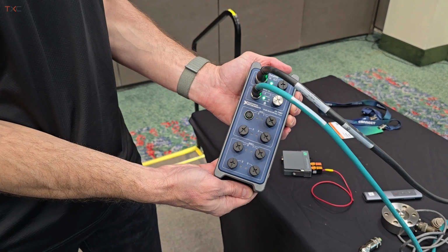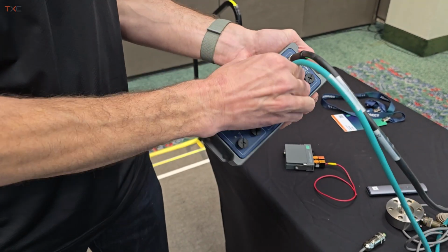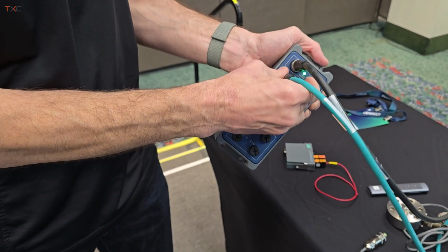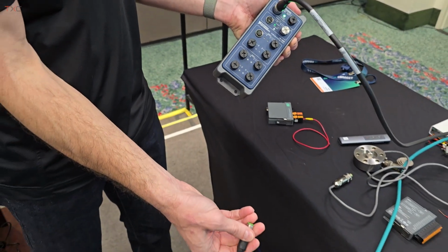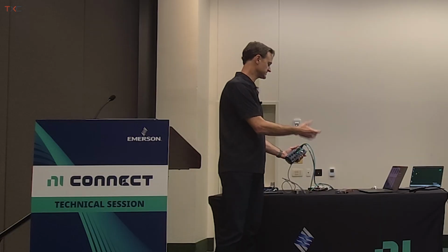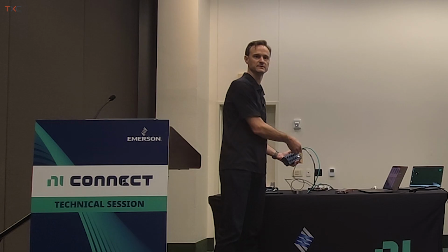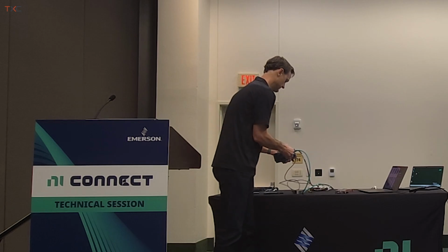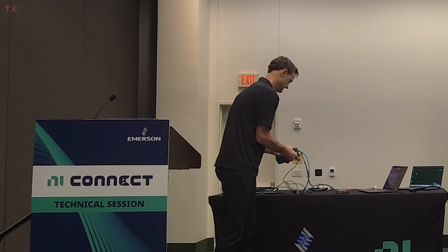So the network, this green wire, if you can see what I'm holding here, this green wire is a network cable. The plugs are M12, so it's a standard industrial connector type. And we have accessories for basically all of them. So if you want to, you can build your own sensor on the M12 and wire it up, kind of like what I've done here. Let me take this off. This is a load cell, and then I've got the M12 connector here, and then this comes apart, and so I can solder, or in some cases screw terminal inside of this and build a very rugged connector type that it doesn't need as much consideration out in the field. It becomes a little bit more hardened for sure.